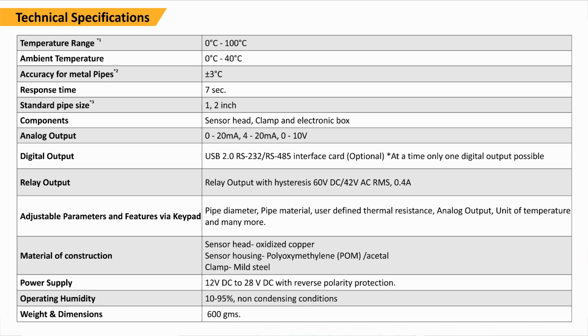The material construction is basically that this sensor consists of two things. One is the heat flux sensor, which is a kind of thermopile, and the other is the surface temperature sensor. The heat flux sensor measures the heat, and the surface temperature sensor measures the ambient temperature. The inaccuracies of the surface temperature sensor are accounted for by the heat flux sensor, and the algorithm is designed in such a way that you will get accurate readings of approximately plus or minus 2 degrees Celsius. So it is a mix of a surface temperature sensor with an algorithm and a heat flux sensor.